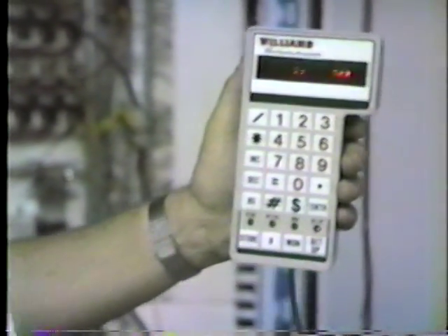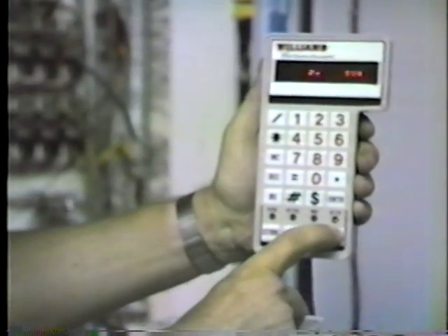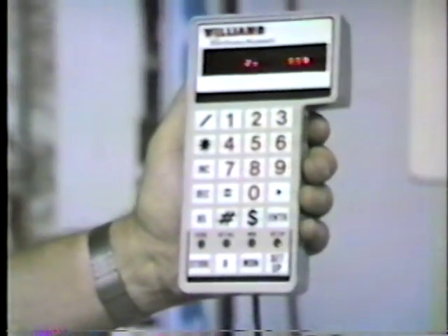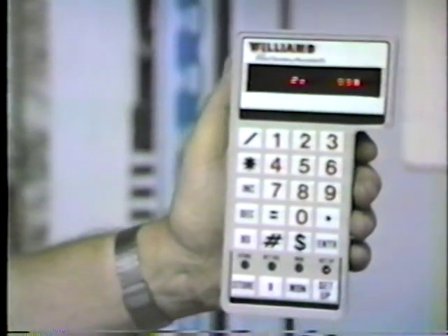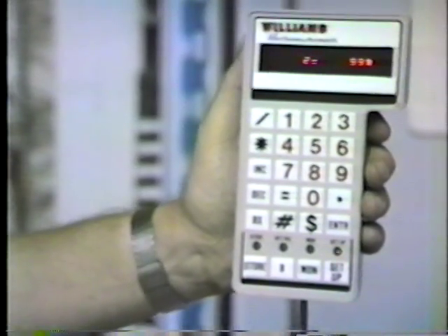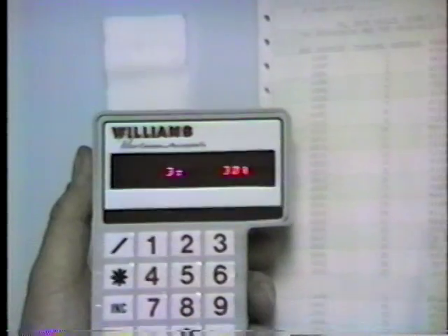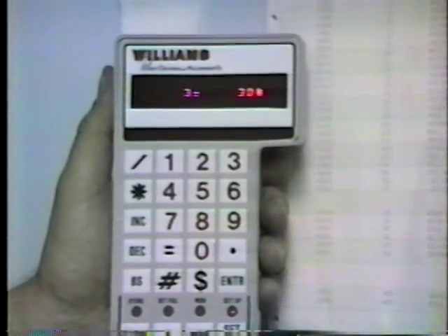And would you step through that and read off? Now I can step through that merely by pushing setup, and now I'm at number 2, and that, as we indicated, is the maximum operating mill speed, 99%. Okay. And let's stop. We have the terminal in front of us. Item 2 is set at 99. That's right. Now item 3 is the spinner speed percent at minimum mill speed. We got ahead of ourselves. We've done 1 and 2. There's 3. 3 is at 30.